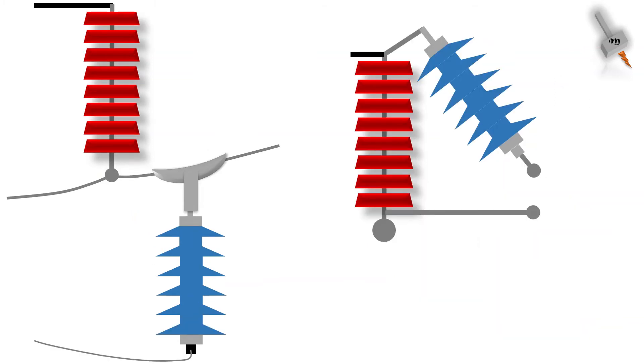Moving ahead, since the NGLA connected in the system are always energized, a leakage current continues to flow through the lightning arrester. In addition to that, the lightning arrester will continuously dissipate heat generated because of the leakage current. As against to that, the EGLA connected in the system are only energized when a lightning surge of magnitude enough to cause a sparkover reaches its terminals. Rest of the period, the lightning arrester has no flow of leakage current or heat dissipation. This is a major advantage with EGLA.